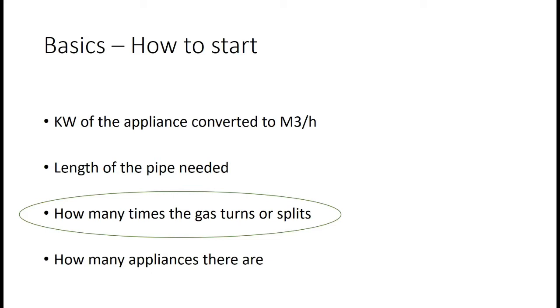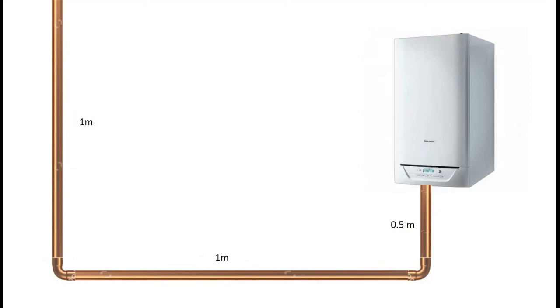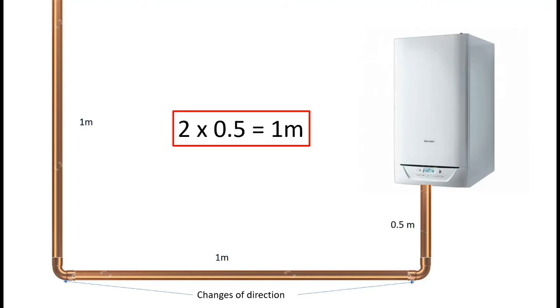Now we move on to the third part, which is how many times does the gas turn or split. In this case it turns twice, once at the first 90 degree elbow and once at the second. Each turn is worth 0.5 of a meter of pressure drop. So we've got two at 0.5 of a meter, so we add one meter to the overall length.